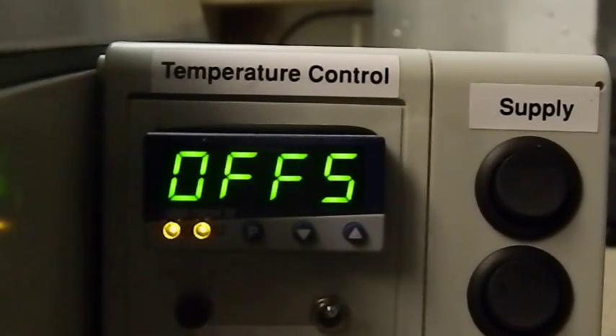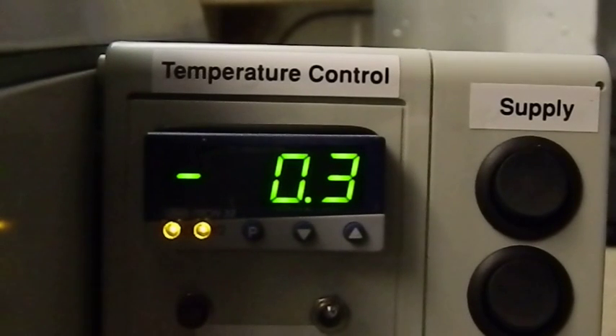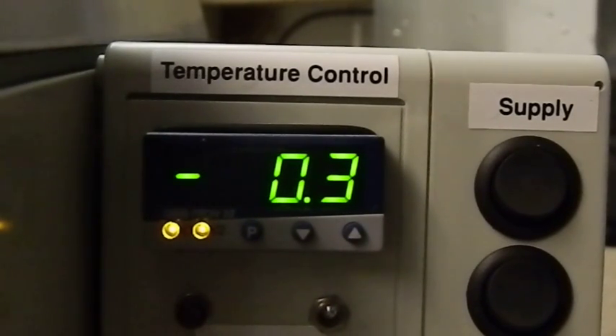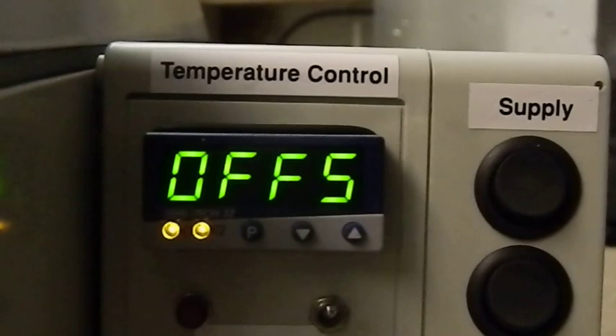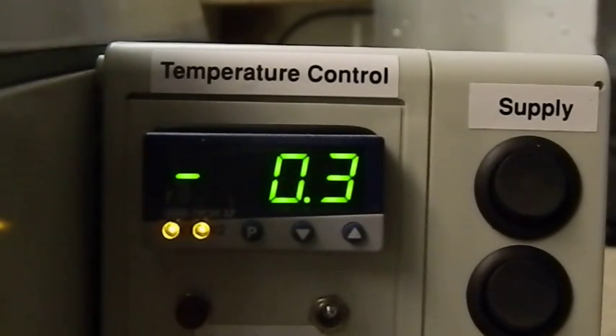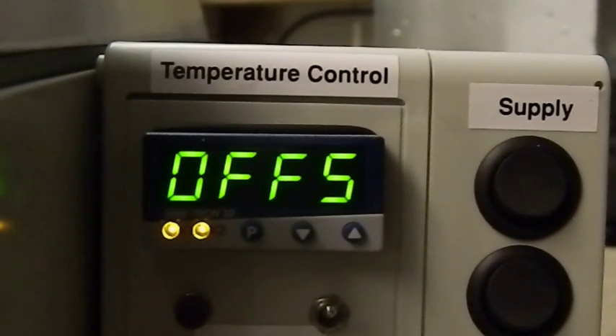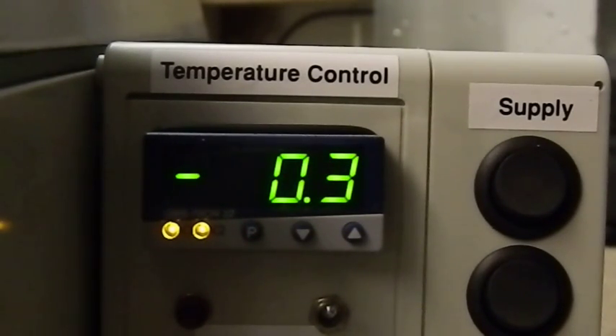Okay, at this point you can just leave the controller alone, and after around 20 seconds it will time out and it will go back to reading the operating temperature. This should now be 0.3 lower than it was when we started, so it should now be reading 13.3. There we go, absolutely spot on cue, and the temperature inside the machine is in fact 13.3. So that is now calibrated.